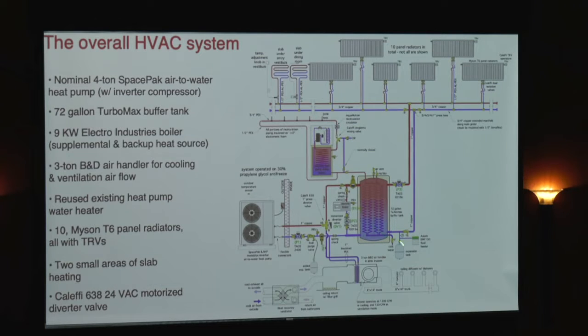So again, the domestic water comes in here, goes up through the copper coils. It gets, I'm going to say, 80 to 90% of its temperature lift right from the water in the shell of the Turbomax tank, and then it goes into the heat pump water heater. And finally, because the plumbing fixtures were spread out quite a bit, we decided to put a recirculation system in there. So there's a little small stainless steel circulator. All that piping is insulated, and that provides more or less instant hot water at the faucet.